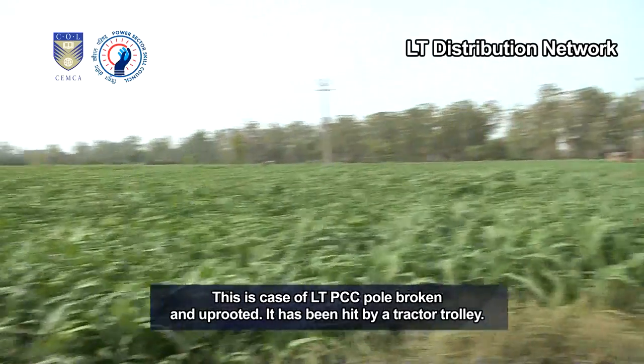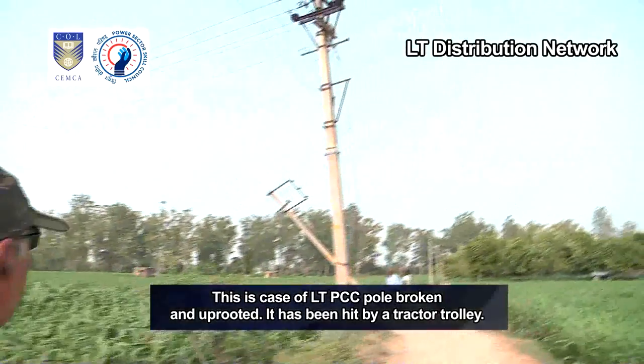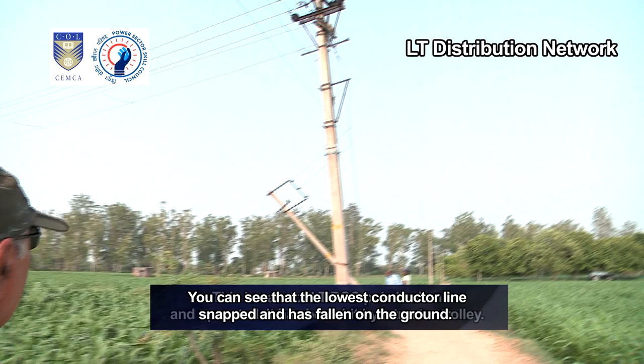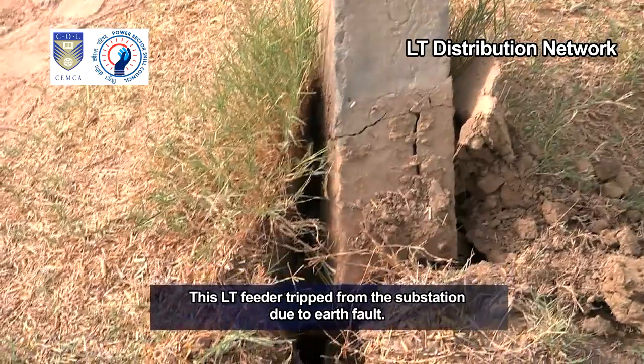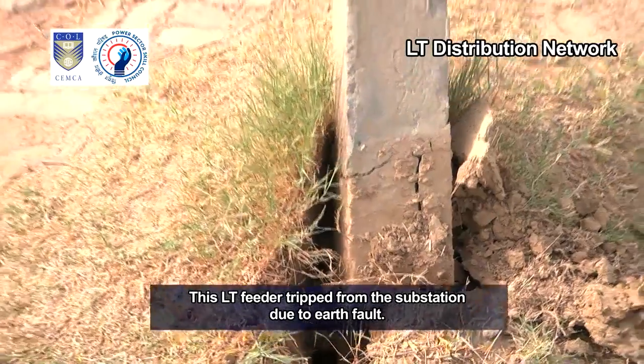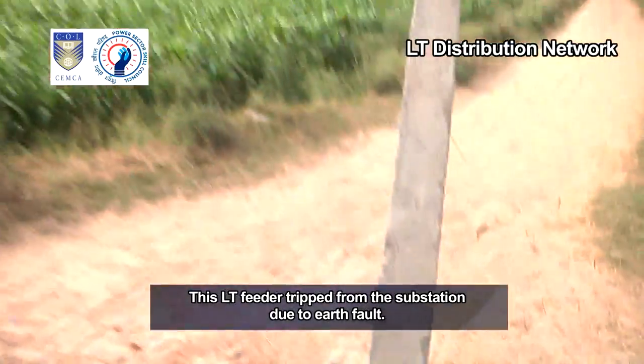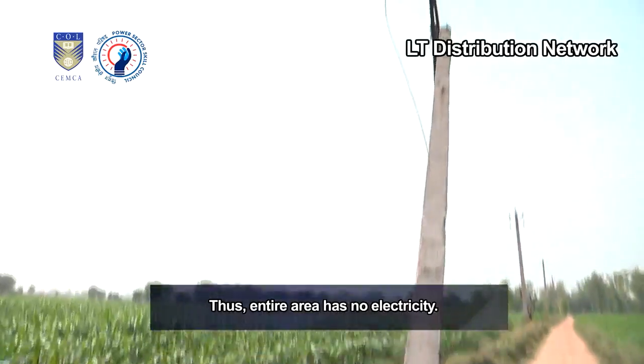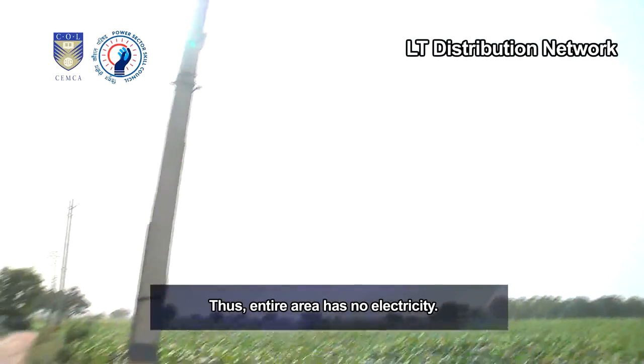This is a case of an LT PCC pole broken and uprooted. It has been hit by a tractor trolley. You can see that the lowest conductor line snapped and has fallen on the ground. This LT feeder tripped from the substation due to earth fault. Thus, the entire area has no electricity.